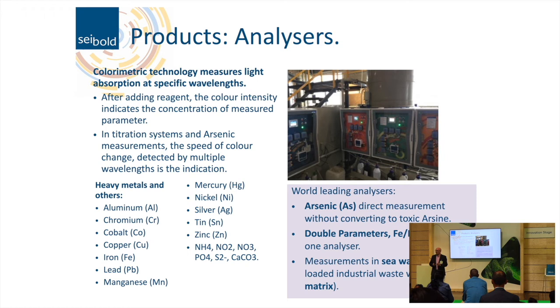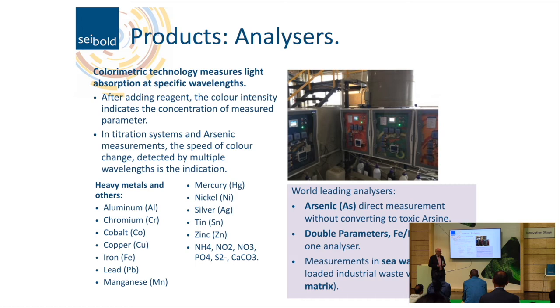The most important analyzers: first is the arsenic analyzer. We do direct arsenic measurements starting at 1 PPB, mostly in the range of 1 to 50 PPB, without converting to arsine — we do not want toxic gases created by our analyzer. We also measure double parameters: iron and manganese together, nickel and copper together, and copper and zinc together in one analyzer.